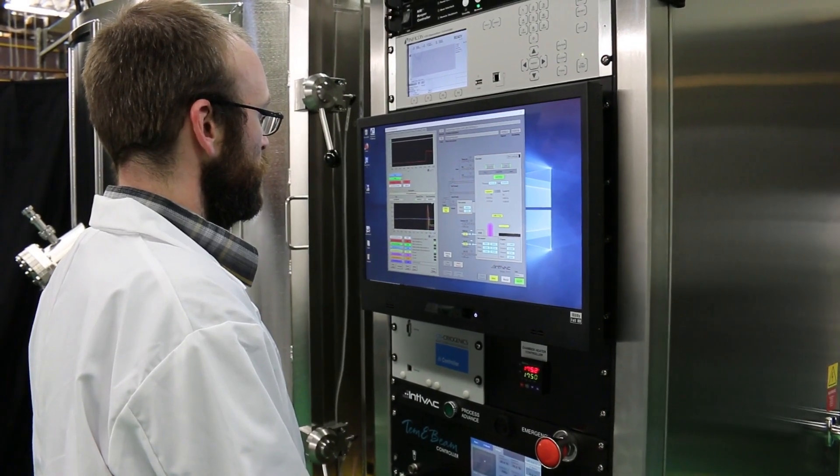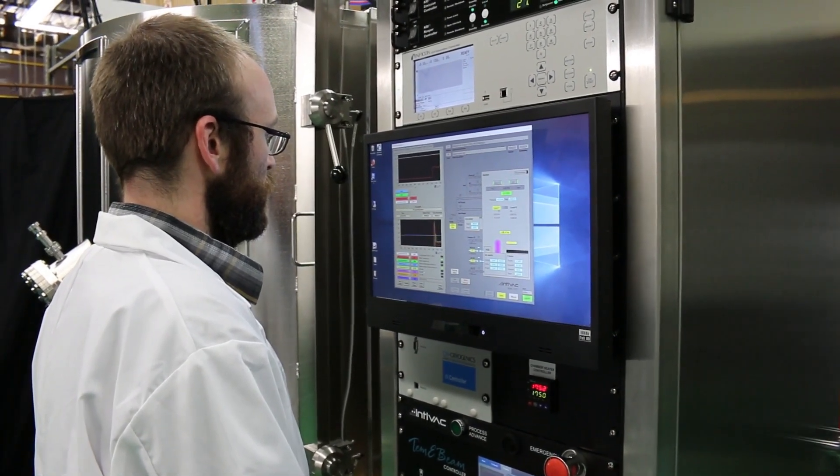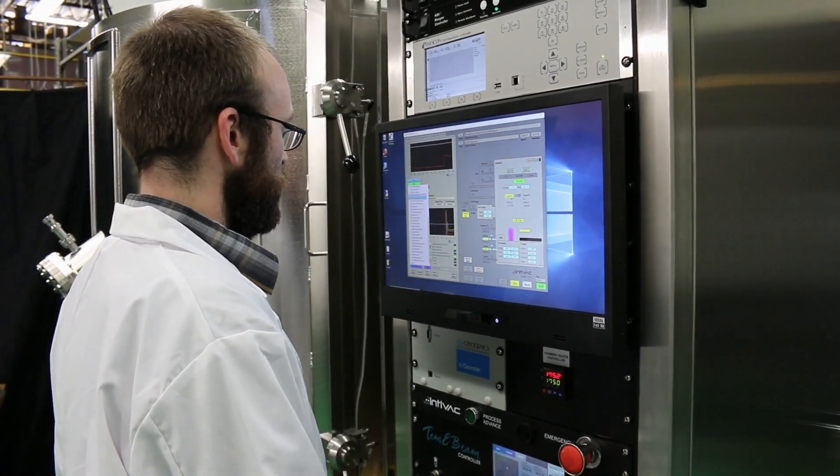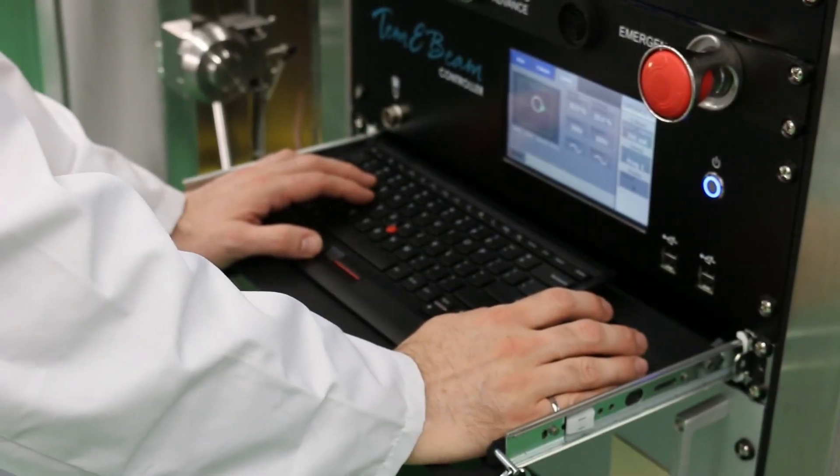The Nanochrome 4 system will make complex optical filters via e-beam evaporation with ion assist under optical control for real-time re-optimization or via standard deposition controls.